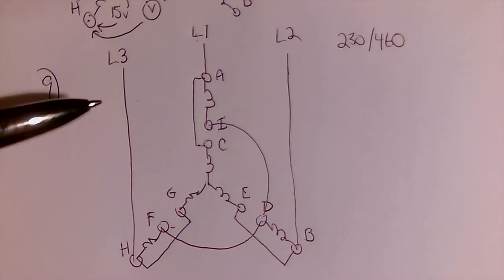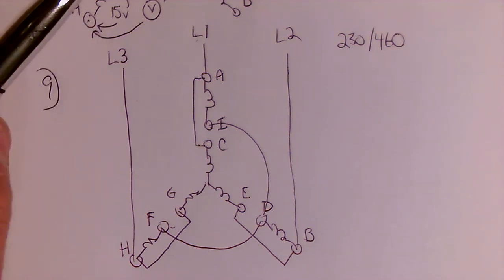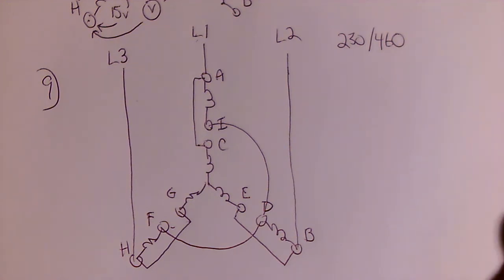And thinking about the NEMA standards. What direction should it spin in? If it was spinning according to standards. From the front, it should spin counter-clockwise. And then looking at it from the back. Which is the drive end. It should spin clockwise.